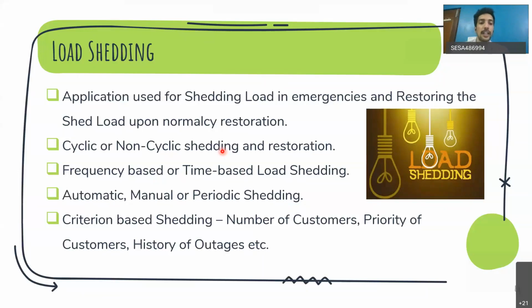Then this shedding can be either automatic or manual or periodic. Automatic means, like in the case of frequency, when it goes below a limit, load is shed and restored automatically. Manual means, as in time-based, at any given moment you get a requirement to increase the frequency and reduce the load. So at that time, you manually shed some feeders.